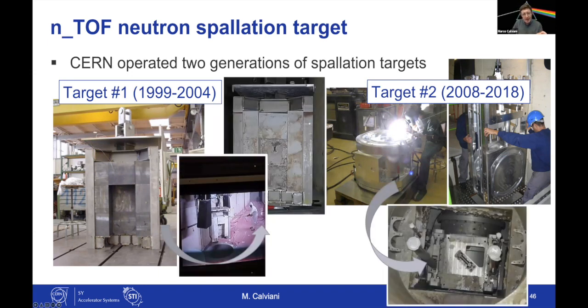The one here on the left, you can see how the target looked like after 4 years of operation. You can clearly see that it changed color, and you can see the point where the beam has impinged. The beam has basically drilled a hole through the lead. You can also see, based on this difference, that the lead basically moved during operation, because, as I said, lead is an extremely plastic material with very low mechanical resistance.